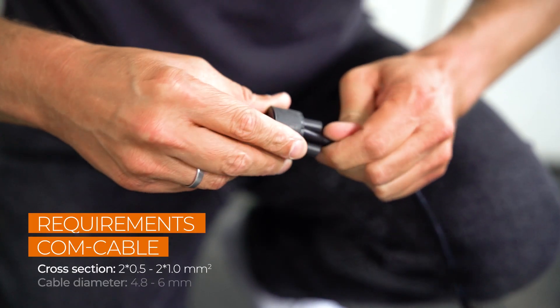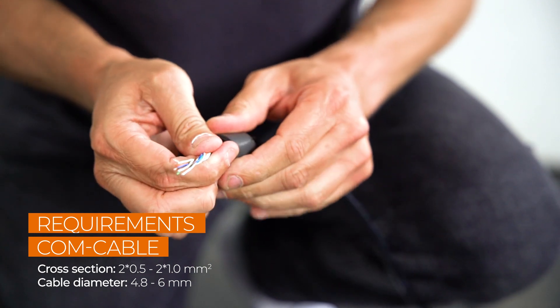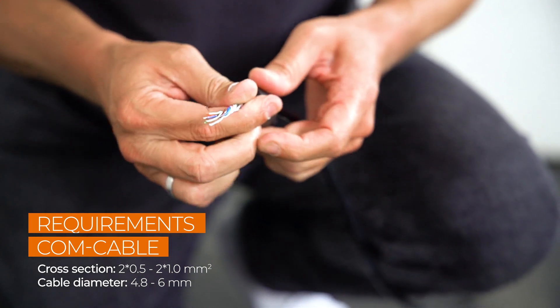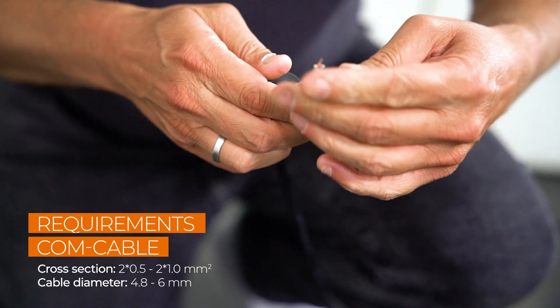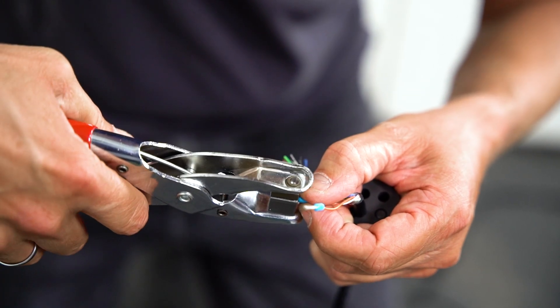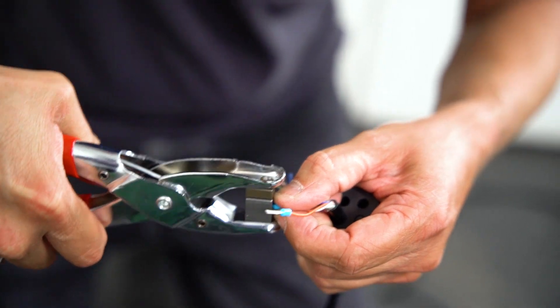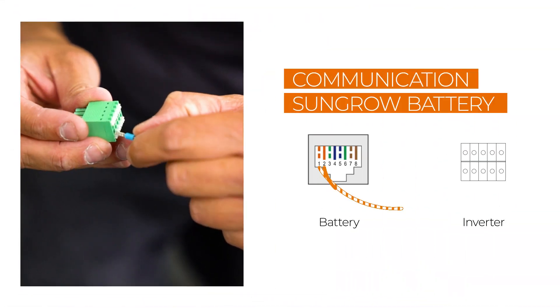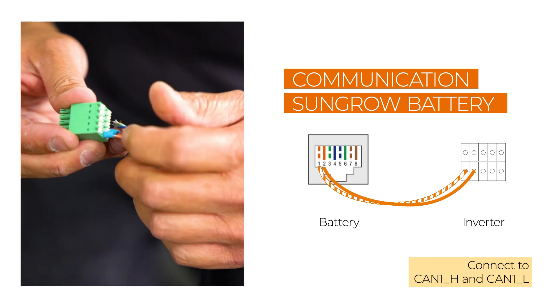Remove approximately 4 to 5 cm of the cable sheath of the communication cables. Then strip approximately 5 to 7 mm of the inner cables. Fit the cables with end sleeves before you push them into the plug. The SunGrow battery is connected to the CAN interface.